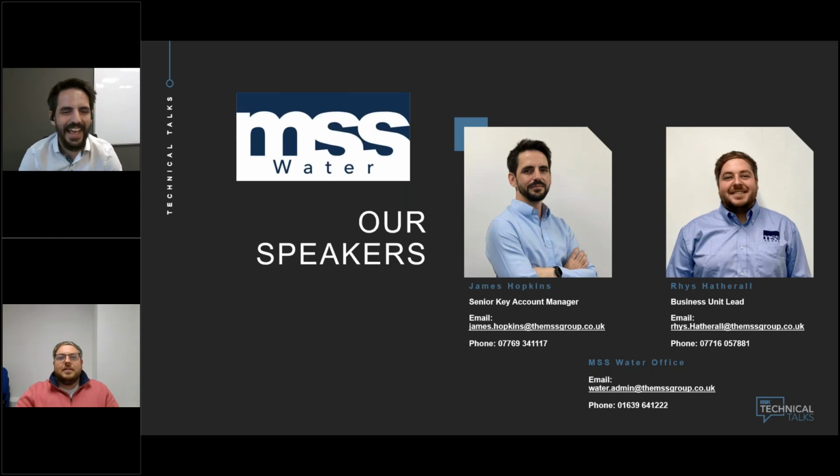Thanks for that, Rhys. So this is quite often a problem area, and not that we have many heat waves in the UK, but when we do, lots of companies will struggle with this. So within England and Wales, water boards are only guaranteed to provide you with mains incoming water less than 25 degrees, but the regulations state that cold taps have to be less than 20 degrees within 2 minutes. So there's that 5-degree difference there, and it's sort of a grey area.